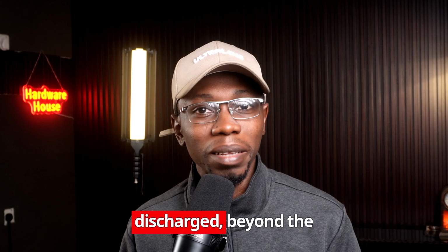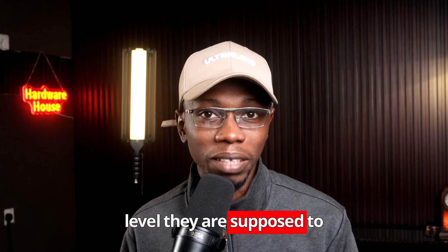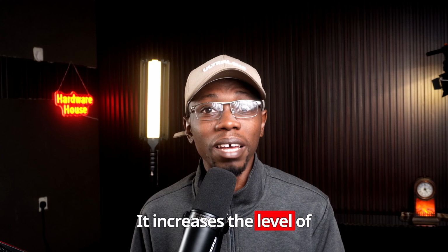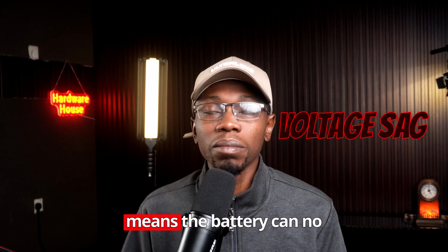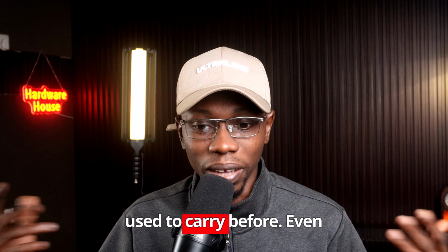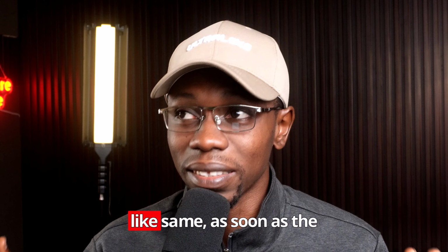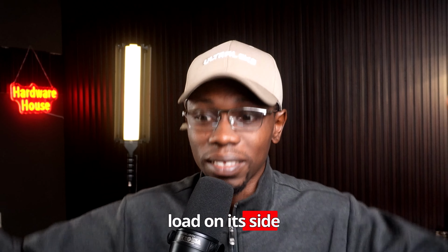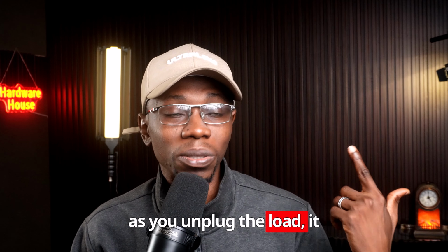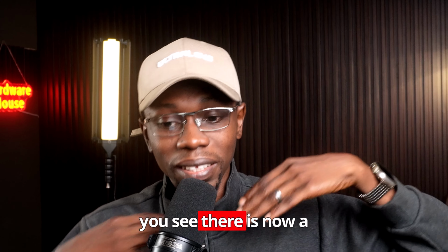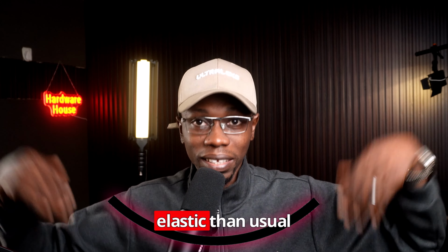When batteries are discharged beyond the level they are supposed to be discharged, it increases the level of voltage sag. That means the battery can no longer carry what it used to carry before. Even though the voltage looks like it's the same, as soon as you put a load on it, it sags immediately. As soon as you unplug the load, it goes back up to what it was. You see, there is now a sagging. It's a bit more elastic than it used to be.